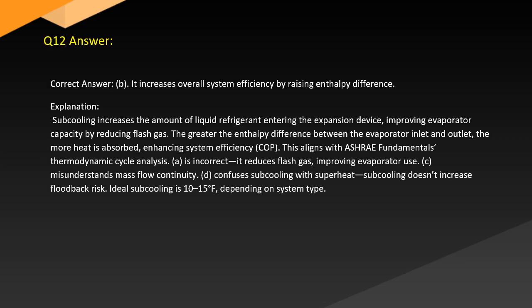Answer. Correct answer: B. It increases overall system efficiency by raising enthalpy difference. Explanation. Subcooling increases the amount of liquid refrigerant entering the expansion device, improving evaporator capacity by reducing flash gas. The greater the enthalpy difference between the evaporator inlet and outlet, the more heat is absorbed, enhancing system efficiency, COP. This aligns with ASHRAE Fundamentals thermodynamic cycle analysis. A is incorrect. It reduces flash gas, improving the evaporator use. C misunderstands mass flow continuity. D confuses subcooling with superheat. Subcooling doesn't increase floodback risk. Ideal subcooling is 10 to 15 degrees, depending on system type.